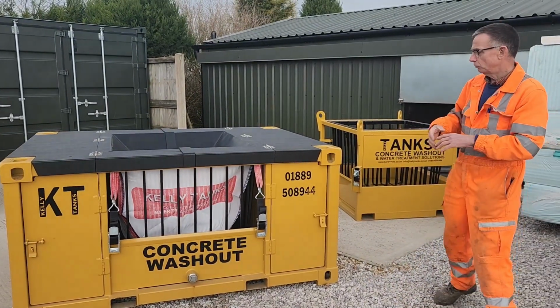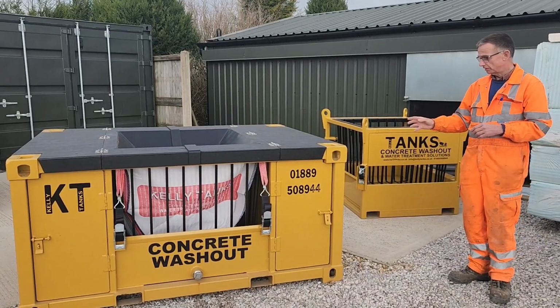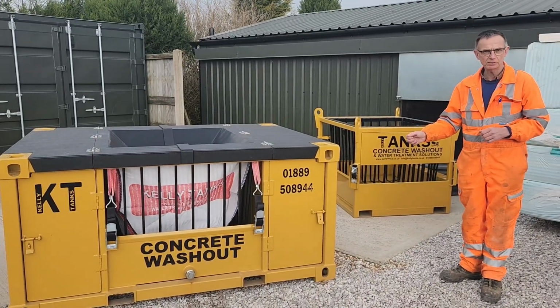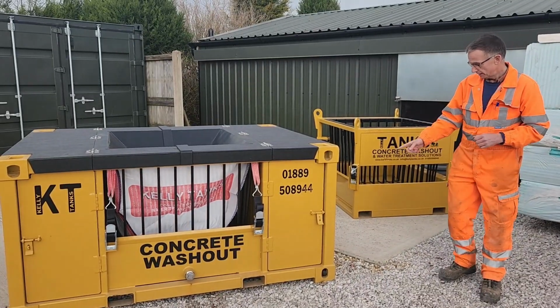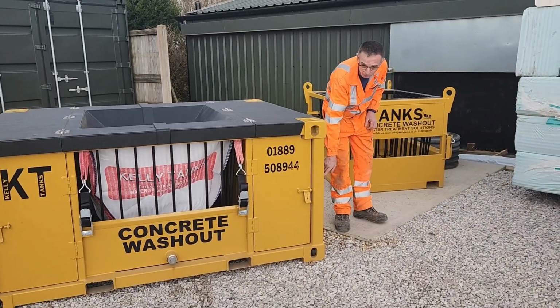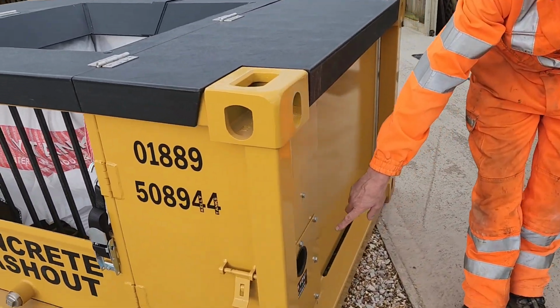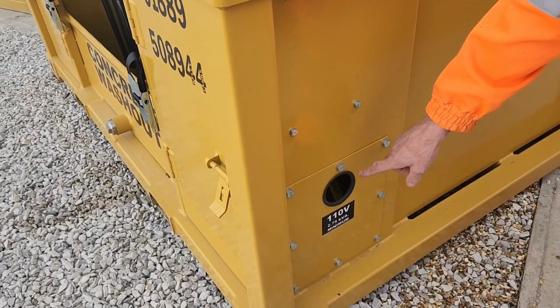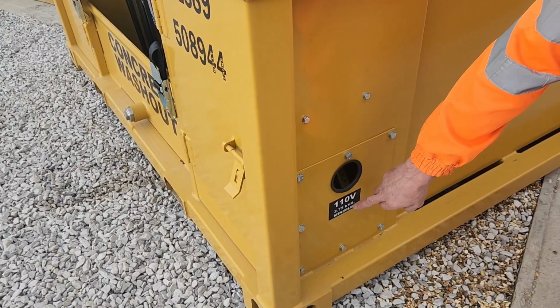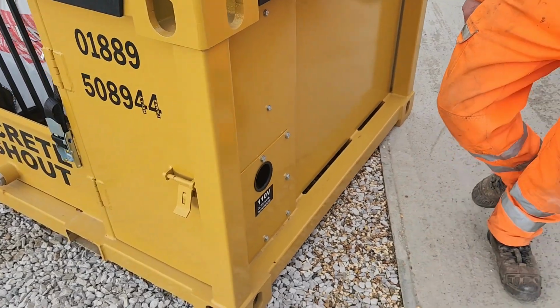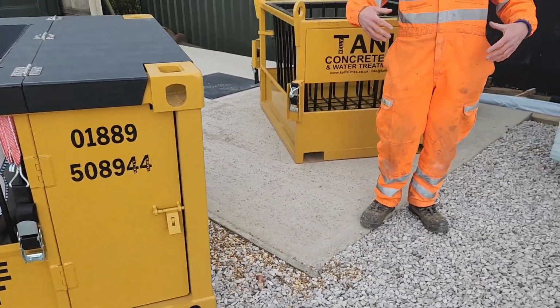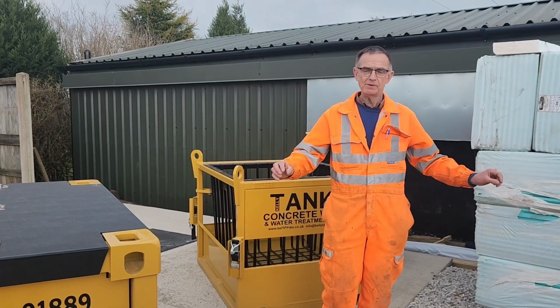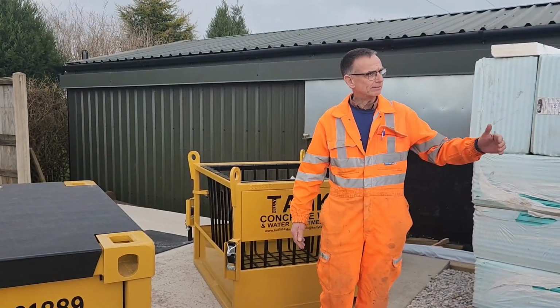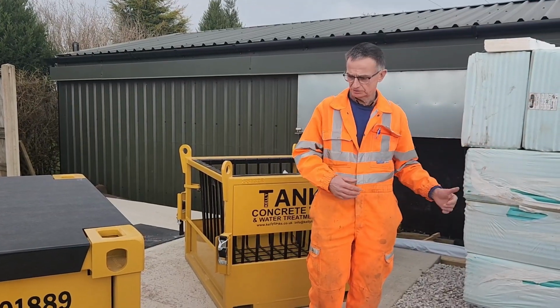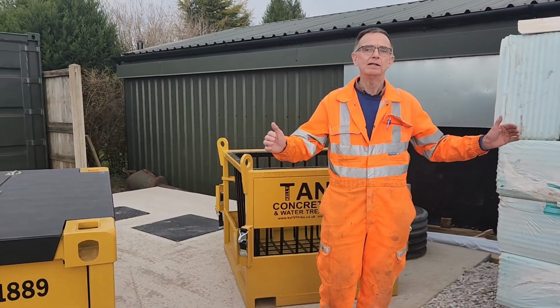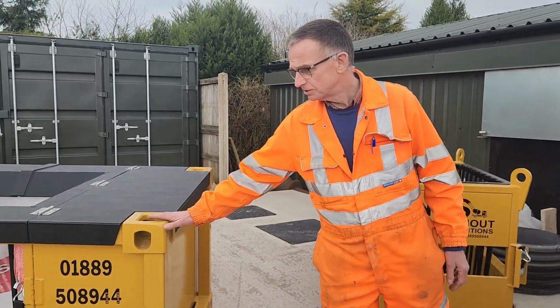Now, all our systems, the Kelly Tanks CWS systems, require 110 volt, 16 amp power supply, and that is located through the hole on the side. Mains power supply straight in. If you're using a generator, please ensure that you've got a minimum of a 2.75 kVA generator, and preferably only one 2.5mm extension cable. We don't need lots and lots of cables joined on, else we're going to lose voltage. It's important that we use just one length of cable to connect the system if using a generator.